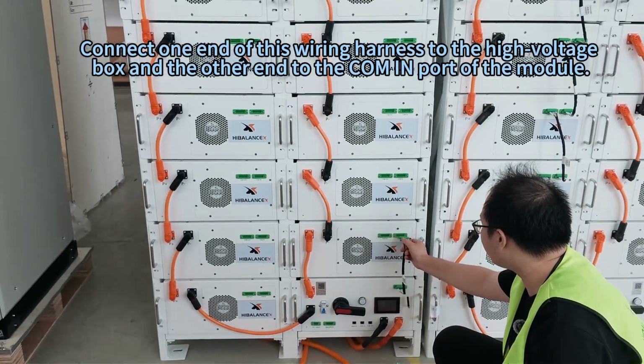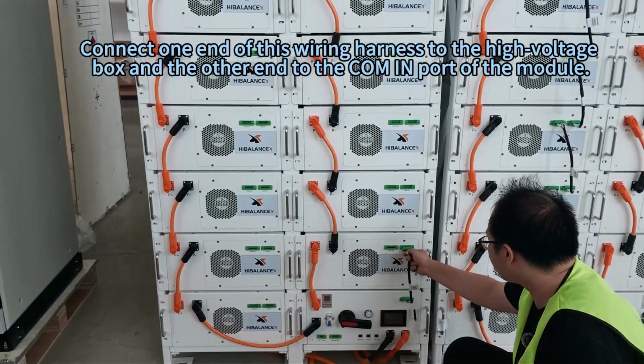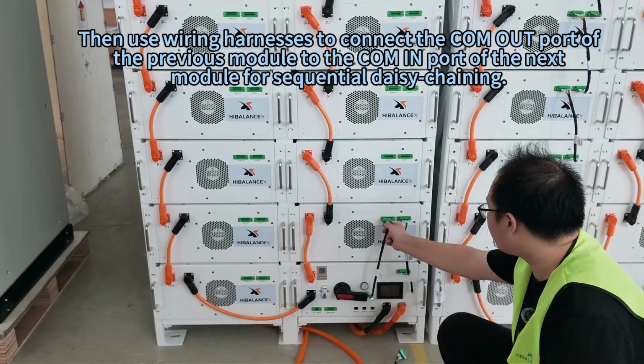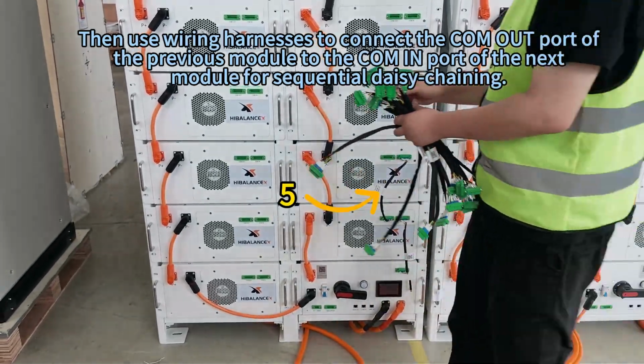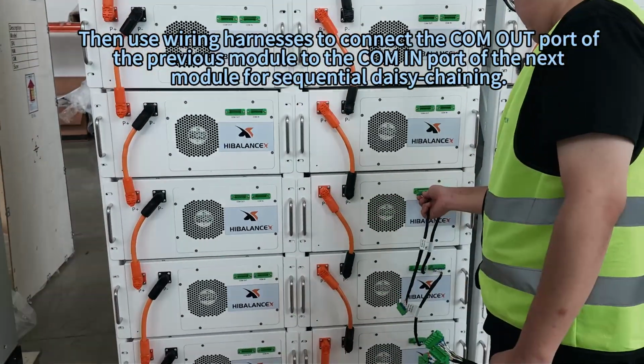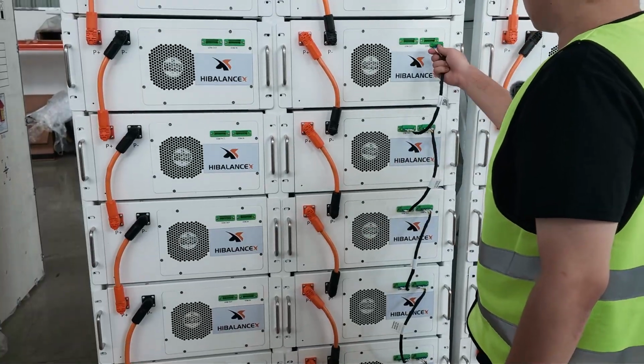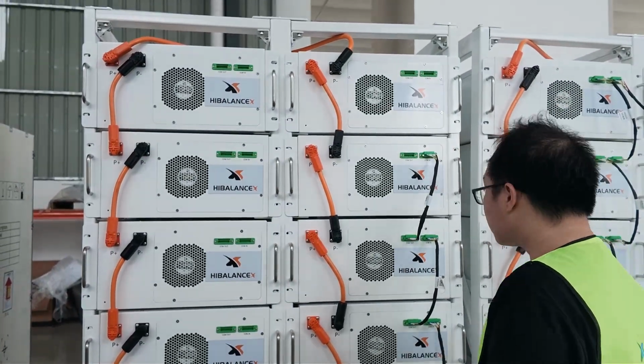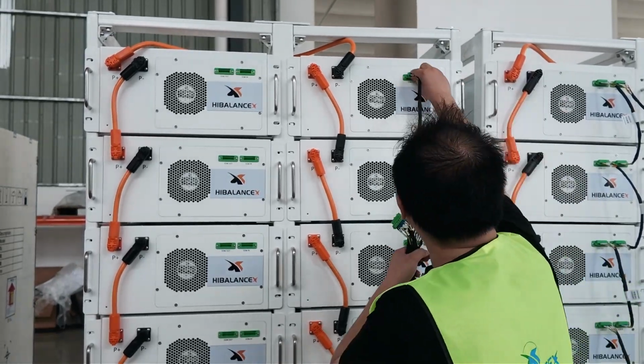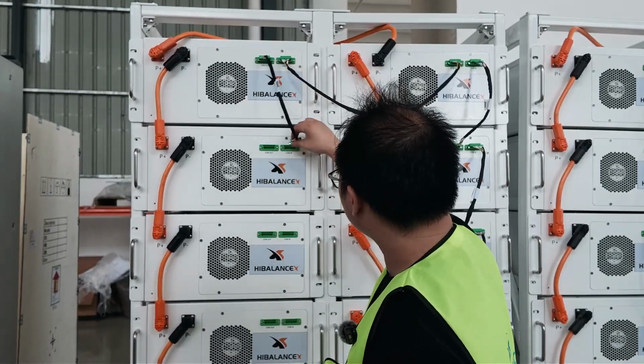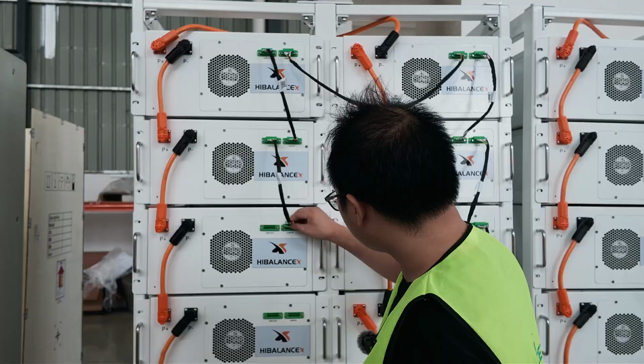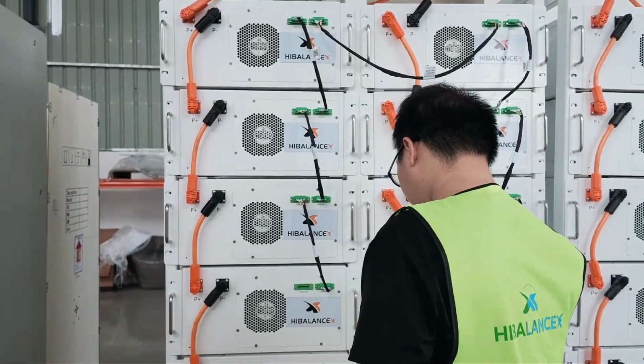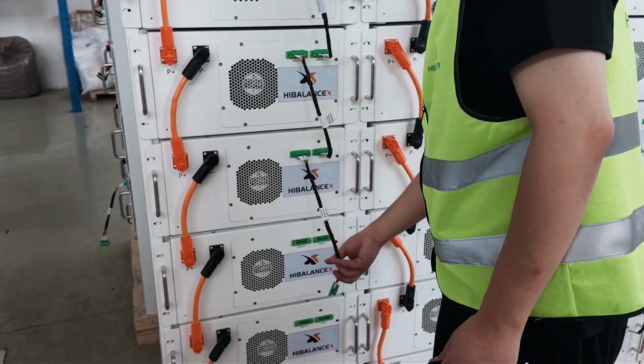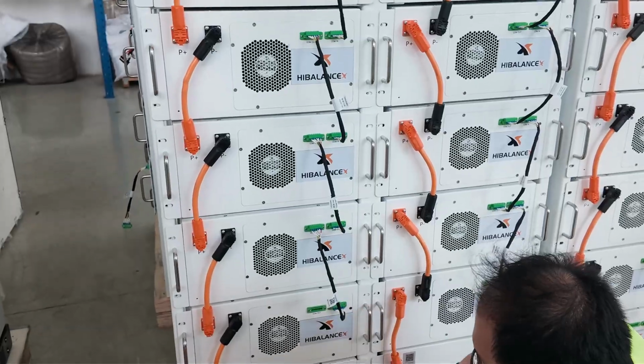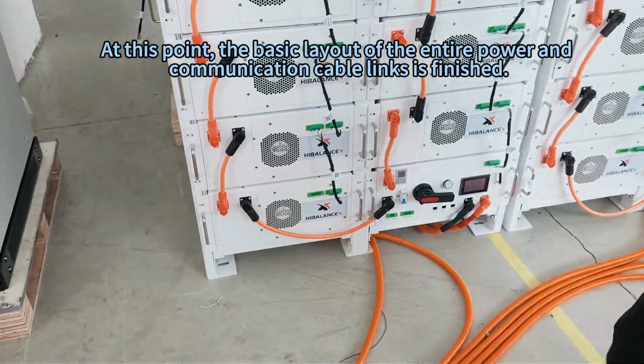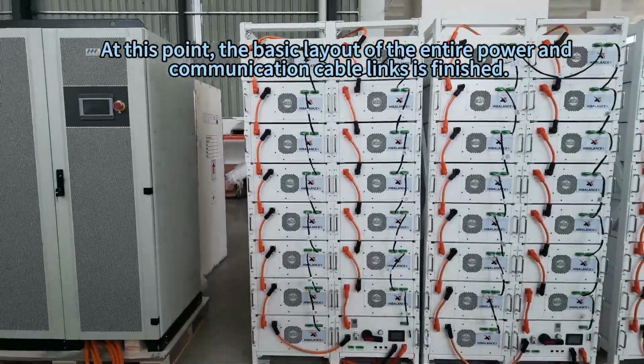Connect one end of this wiring harness to the high voltage box and the other end to the COM IN port of the module. Then use wiring harnesses to connect the COM out port of the previous module to the COM IN port of the next module for sequential daisy chaining. At this point, the basic layout of the entire power and communication cable links is finished.